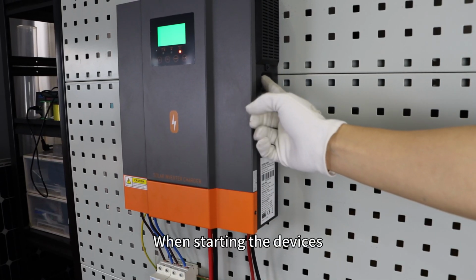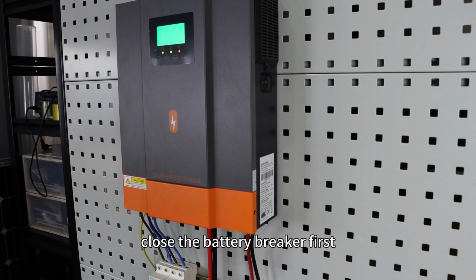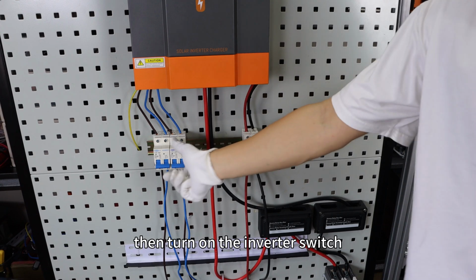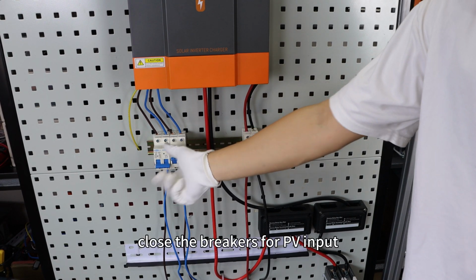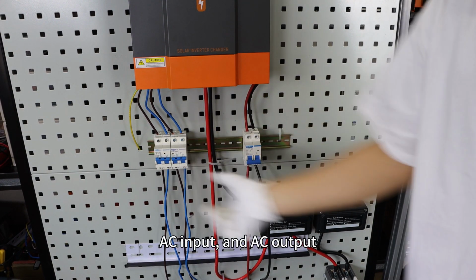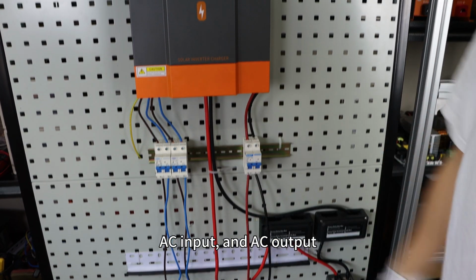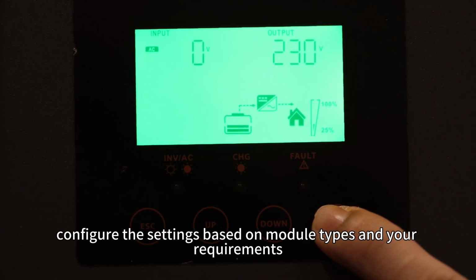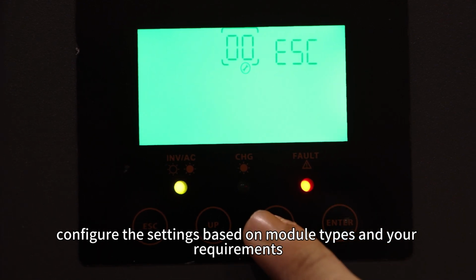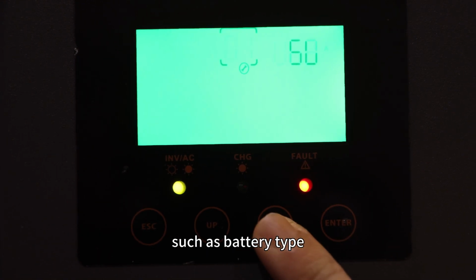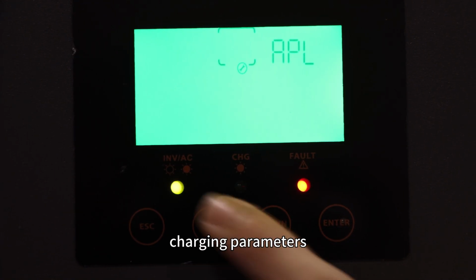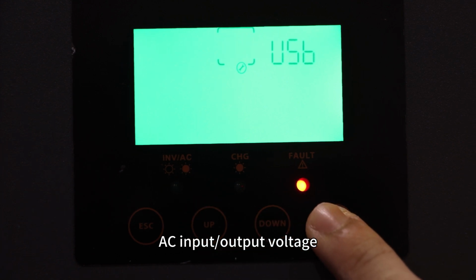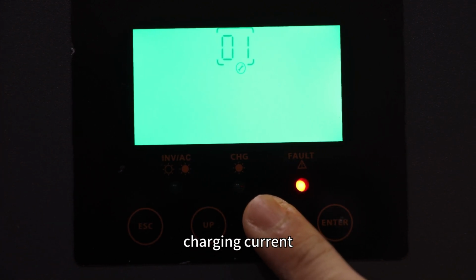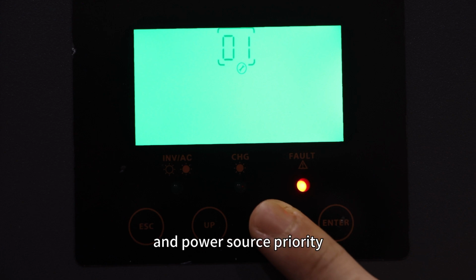When starting the device, close the battery breaker first, then turn on the inverter switch. Afterward, close the breakers for PV input, AC input, and AC output. After startup, configure the settings based on module type and your requirements, such as battery type, charging parameters, AC input or output voltage, charging current, output priority, and the power source priority.